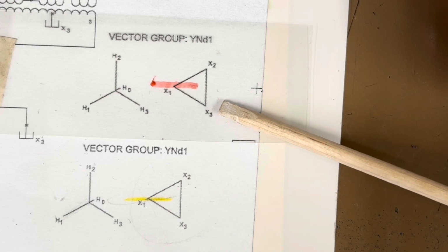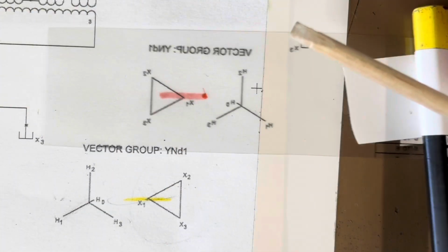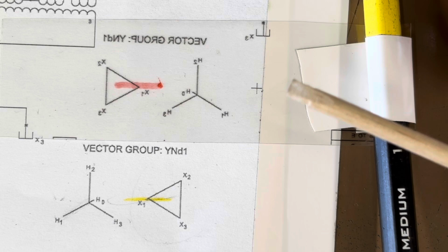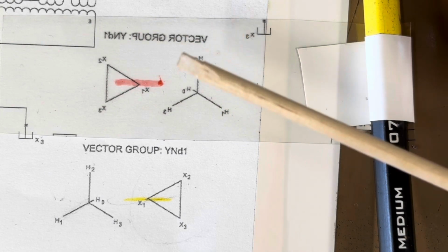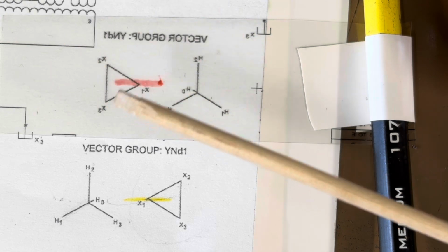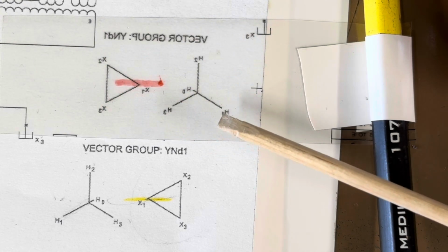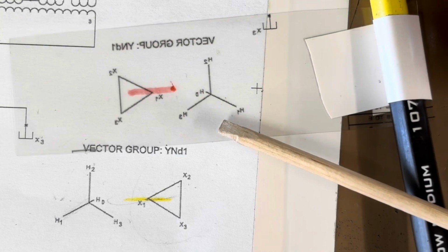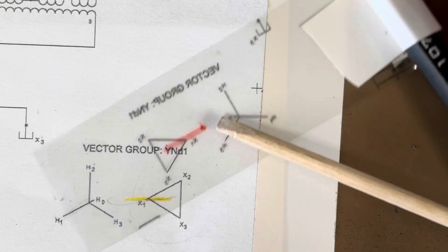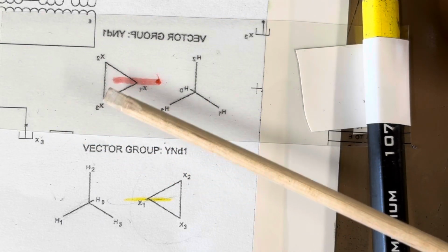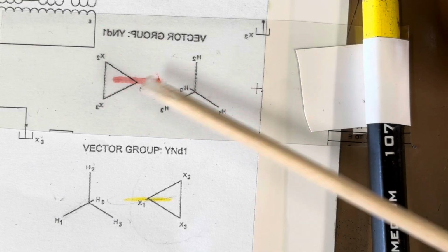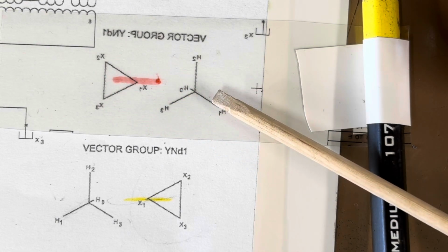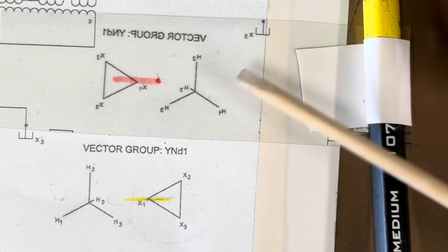Now, if you were to take the same transformer and apply backwards phase sequence to it, you basically invert the nameplate. It's almost like you're looking at it from the back. So H1, H2, H3, X1, X2, X3. And you could see that if you were a little stick man standing where this stick is and this was rotating, it would be 1, 3, 2 phase sequence. Now, same transformer constructed the exact same way, the secondary leads the primary by 30 degrees or lags by 330 degrees.